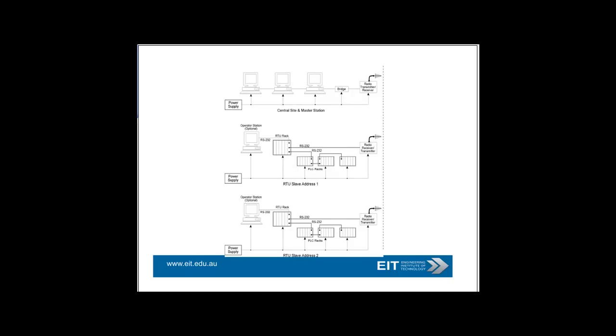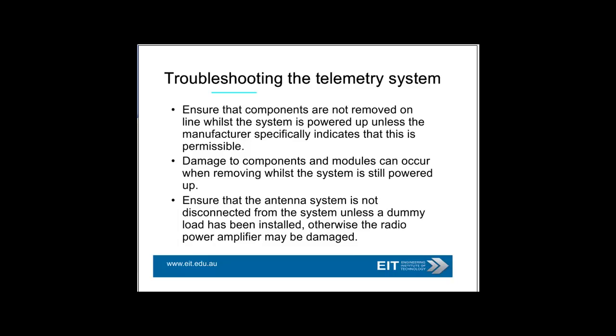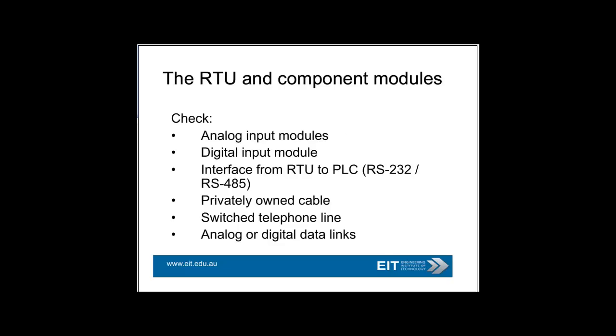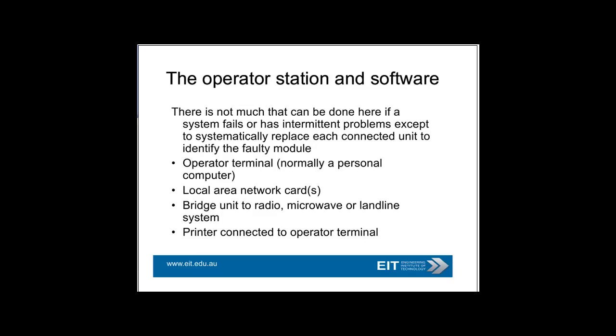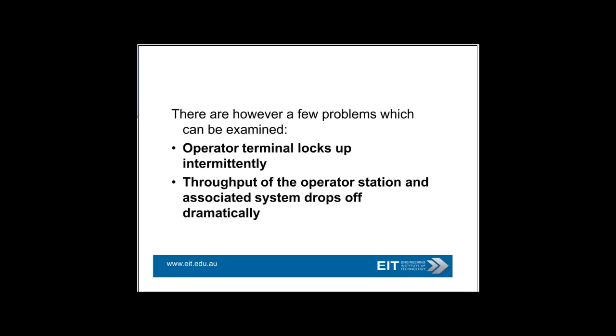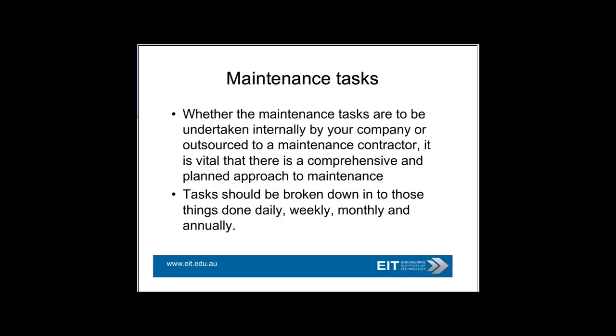When troubleshooting, don't remove components online because you may have a problem with failure of components. With antennas, make sure that your dummy load is installed, otherwise you may have a problem with your power amplifier and fire risk. Typical components that need to be checked include your analog inputs, digital inputs, and the RTU. Also check operator station software, network cards, and other things like the bridge or switch. Typical problems include operator terminal locking up intermittently and a dramatic drop-off in data. You could find issues with noise and interference causing those sort of problems.